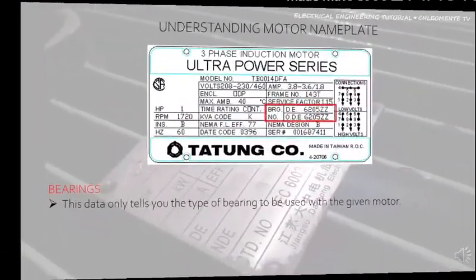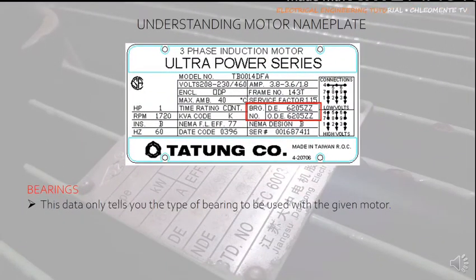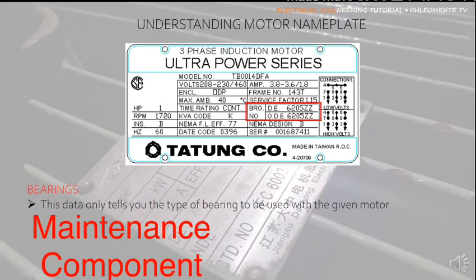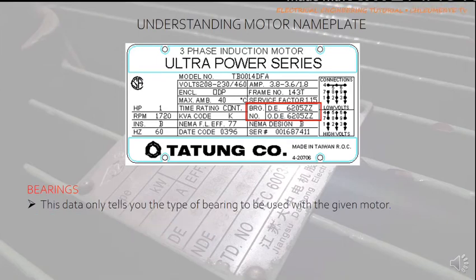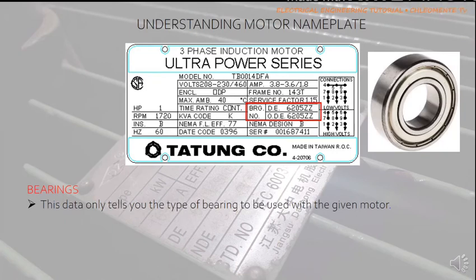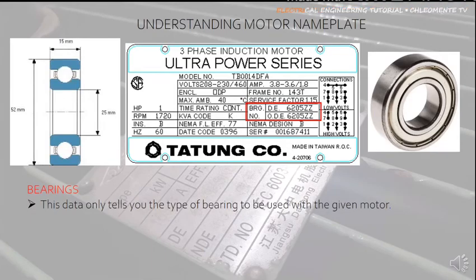Bearings: Though NEMA does not require it, many manufacturers supply bearing data on the nameplate because bearings are the only true maintenance components in an AC motor. This is very important data for maintenance personnel. Some larger motors require proper lubrication. In this example, 6205ZZ bearings for both drive and opposite drive ends means a ball bearing, double seal, with a 25mm bore and 52mm outer diameter.